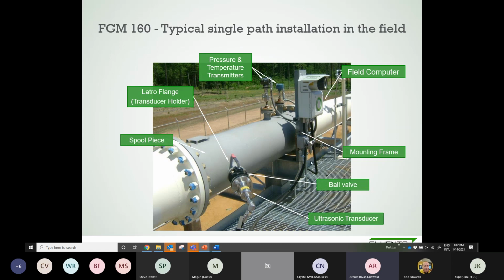And then you see the spool piece. This is a spool piece version. One little thing about this arrangement is that we have a ball valve connected between the nozzle that's welded to the pipe and the sensor. The idea with this ball valve is that we have the ability to retrieve the sensor online without shutting in the pipe or stopping the process per se. In regular operation, nobody wants to stop the flare line. That allows us to pull the sensors, safely remove them, and put them in a zero box to do the calibration or the verification that I mentioned before.